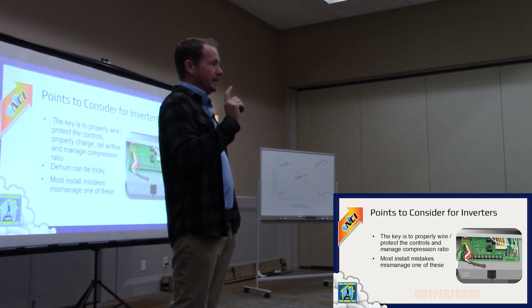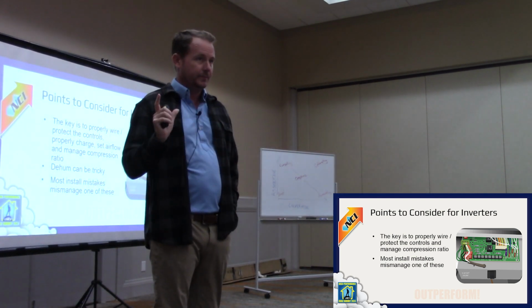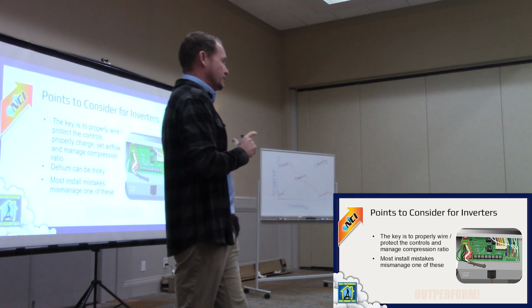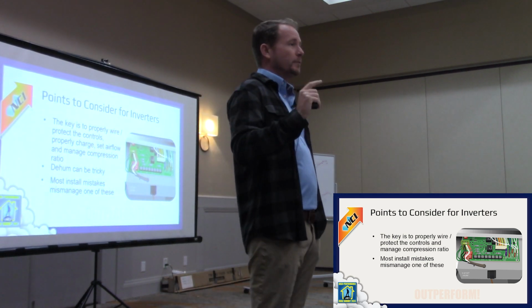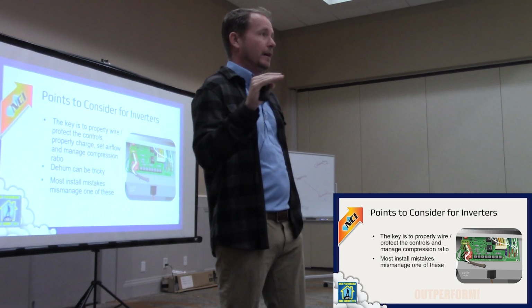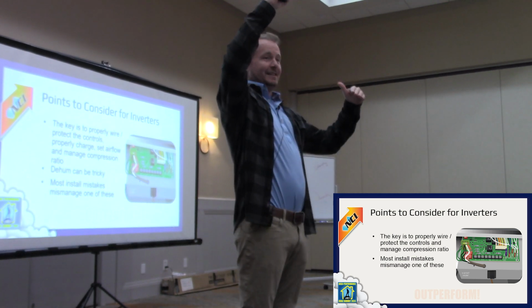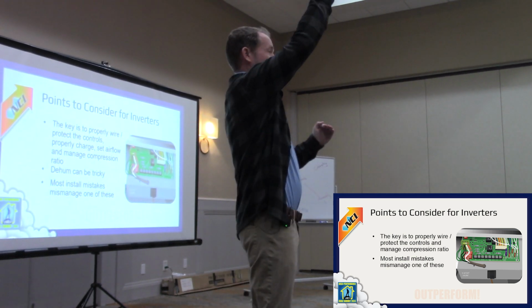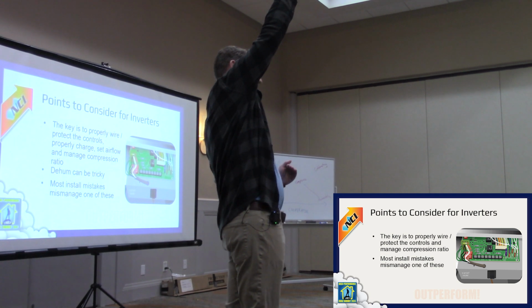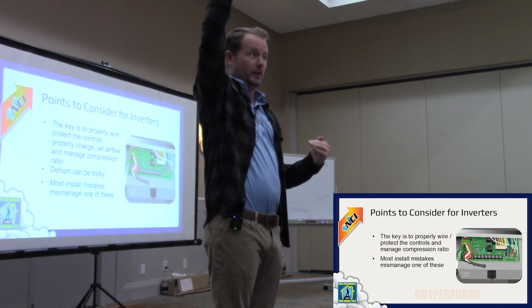Almost everything you run into is a problem with one of those. Managing compression ratio is a tricky one, because all compression ratio means is the difference between your head pressure and your suction pressure. The further they are from each other, the more inefficiently the system operates.